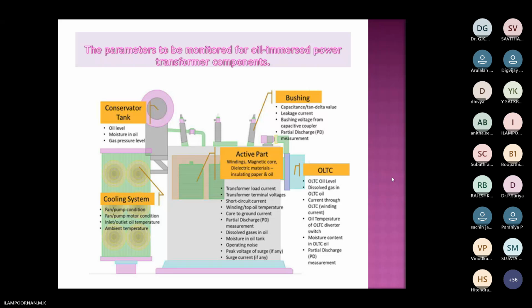Air forced cooling, sir, we use forced cooling in the distribution transformer. Yes, sir. No, it's a natural convective flow, or you will use fins. There is no pump to pressurize the oil - only when there is a pump, it is forced. So it's a normal flow of oil through the fins. They call it natural oil flow, right?